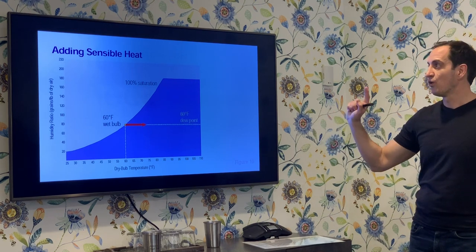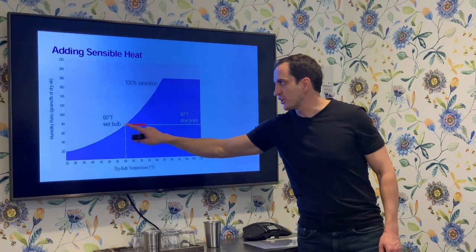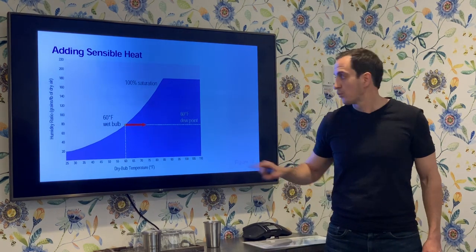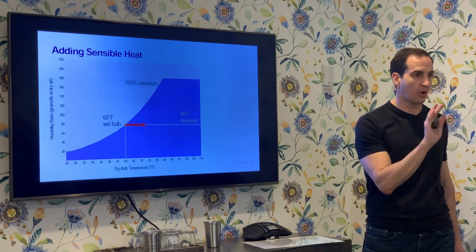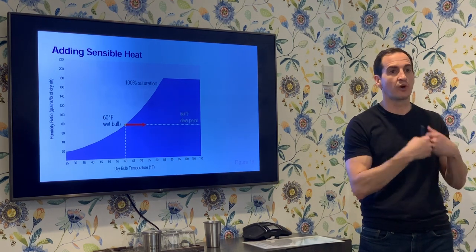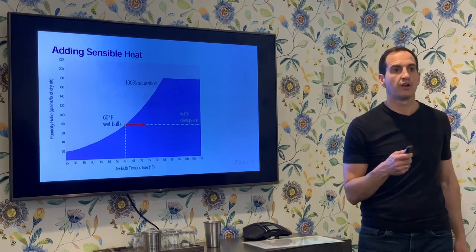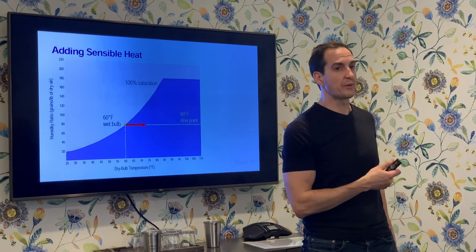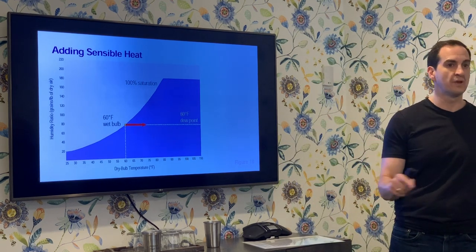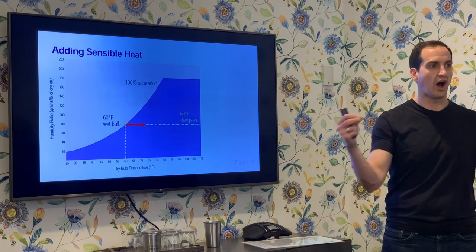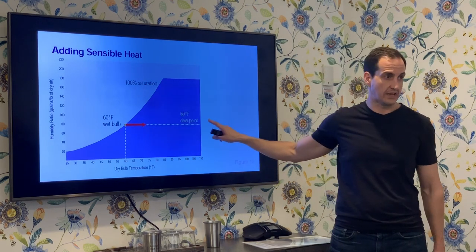When we add sensible heat, we start at a saturation condition and add temperature-only energy — nothing to do with moisture addition. This is exactly what happens in a grow room when we turn the lights on with no plants and no people in the room. It is a dry box with hot electric elements that make light — this is sensible addition of heat only.